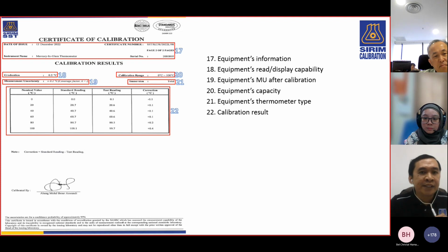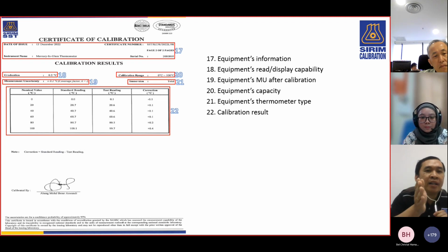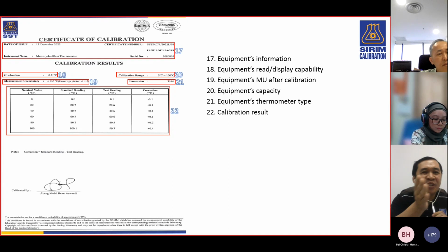Okay, so as you can see, there are 4 columns there. Nominal value means the value that we set during calibration. Standard reading is our calibration reading. Test reading is the user's equipment, and the correction is how much error between the user's reading and the standard reading.